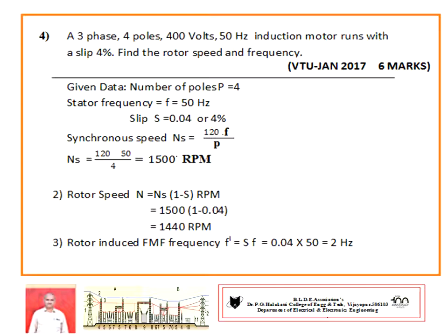Then he asked the rotor induced EMF frequency. You use the formula F dash equal to S times F. F is supply frequency. Again S is the fractional value, 0.04 into 50. We are getting the answer as 2 Hertz.